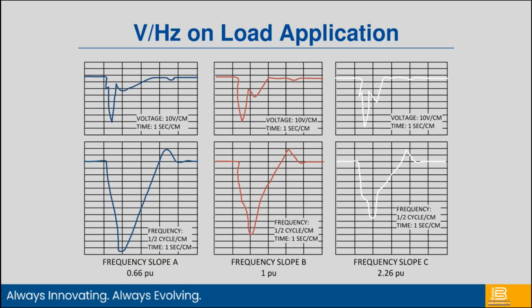So in this case, we have three different slope frequencies. We have a 0.66 per unit, a 1 per unit, and a 2.26 per unit volts per hertz curve. So at the 0.66, I'm not decreasing my excitation as much. And you can see at the bottom of that graph, this is one all the way to the left, my frequency drops pretty low. If I go to a 1 per unit, my frequency doesn't drop quite as much. And if I go to an even more aggressive slope of 2.26 per unit, I have even less of a drop in my generator frequency.